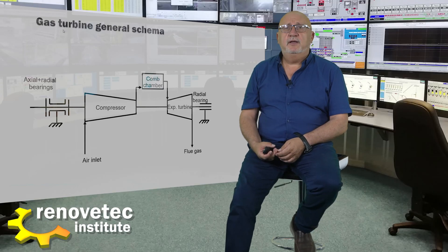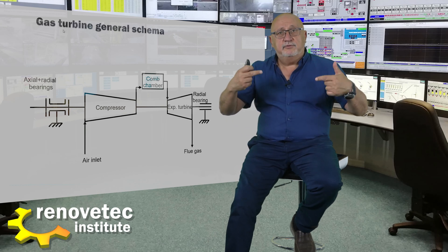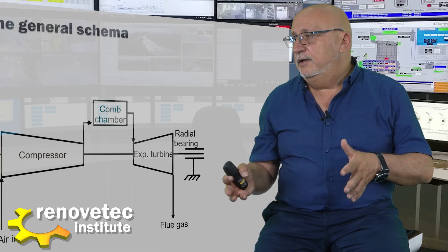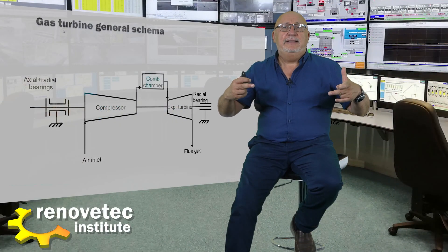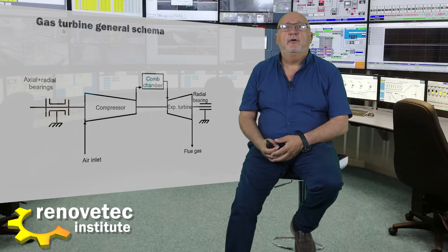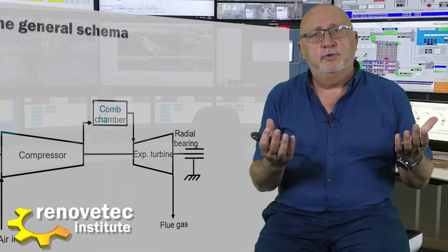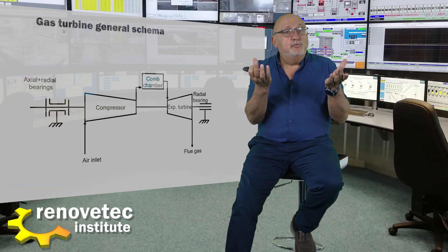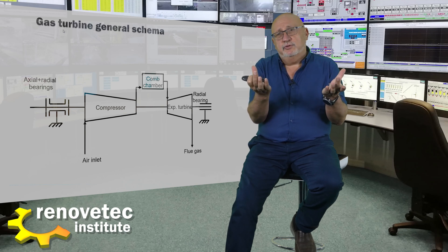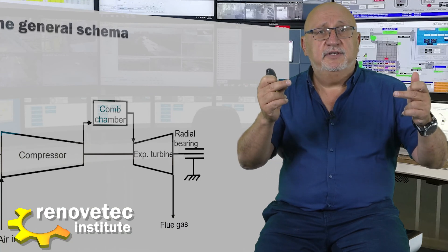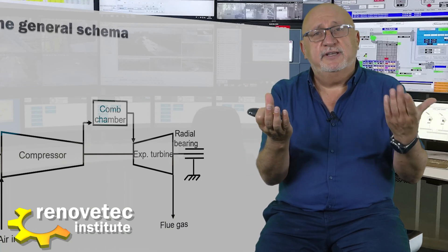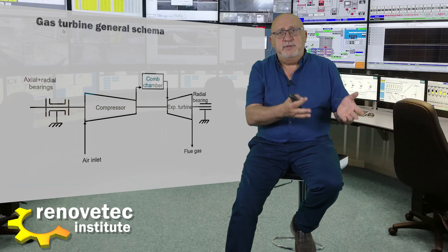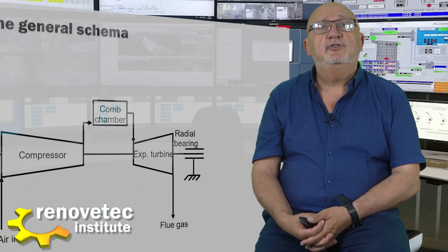The compressor and expansion turbine are rotating, and they can turn on the same shaft or not, depending on the type of turbine. When we have a shaft, we need to support it at least at two points. To absorb the friction provoked by this movement, it is necessary to install bearings. The bearings could be rolling bearings or journal bearings, and we need at least one at each side of the shaft.